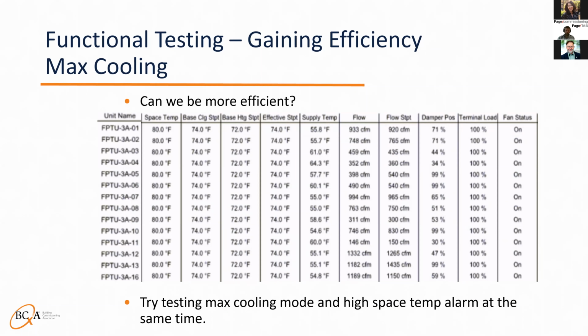And let's look at a couple. Looking at FPTU 3A 5, 6, 10, and 13, the damper is 100% open and cannot meet flow set point. If the AHU is maintaining its static pressure set point and there is no diversity in the system, then the static pressure set point is not correct. Now look at FPTU 3A number 4. Discharge temperature or supply air temperature is too high. The AHU is delivering 55 degrees, yet the terminal unit is delivering 64 degrees. Either the box has lost its calibration or was never properly neutralized by TAB in the first place. This will obviously create cooling issues in the future.